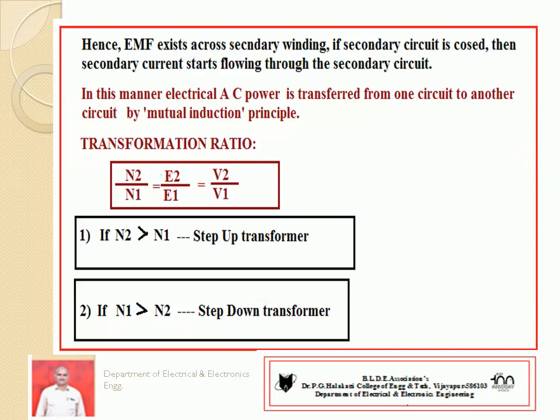As per the turns ratio, we have two types of transformers: step-up and step-down. Step-up means voltage is increased — for example, in a power plant, 11 kV voltage is generated and it is raised to 220 kV. Such a transformer is referred to as step-up. Step-down means voltage level is reduced from primary to secondary. Step-up transformers are observed in generation units, while step-down transformers are used in household applications. For example, the connection taken from the pole is the secondary of a transformer giving 230 volts output, with 11 kV as the input line.